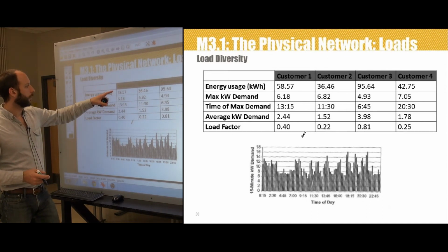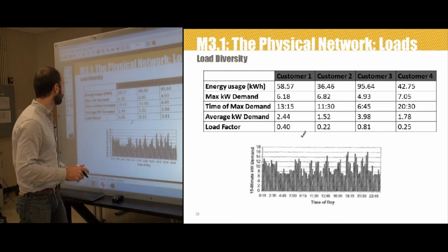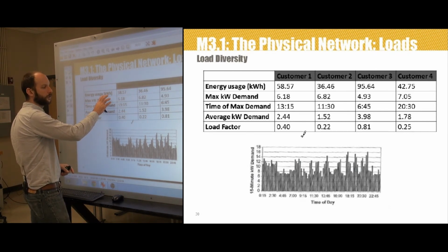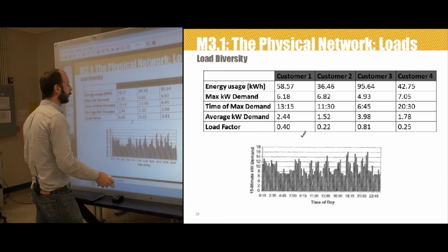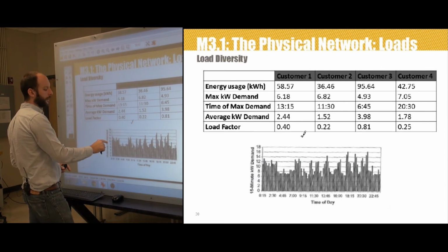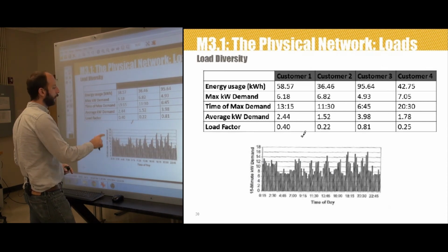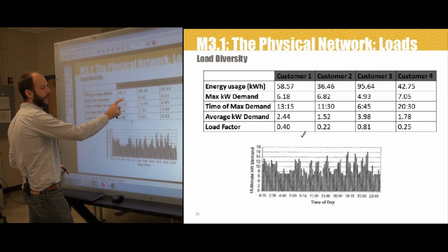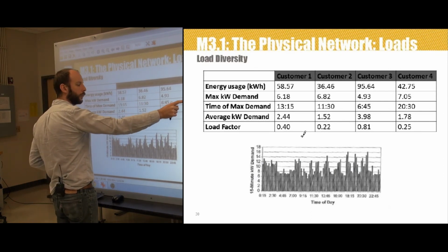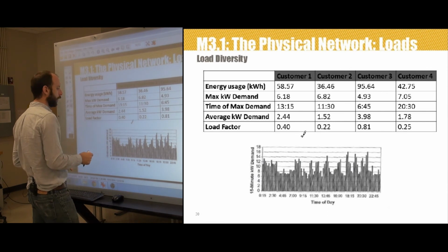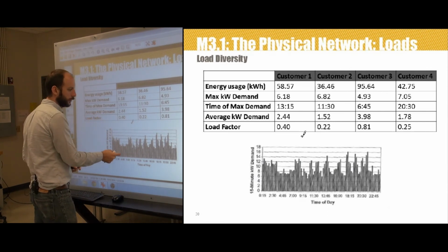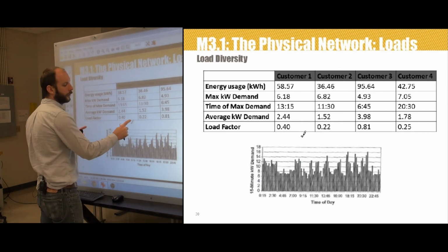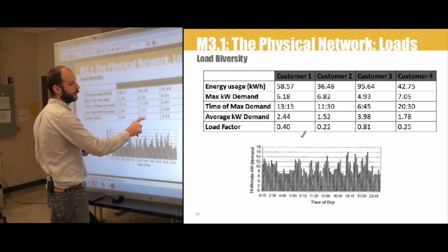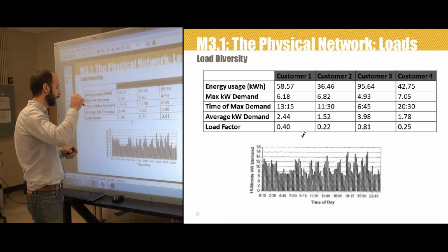What we've got is customer 1, customer 2, customer 3, and customer 4, and they all have different energy usage. Remember, that's the total amount used over the course of the day. They've got different peaks. That's the biggest one. They've got different times that the peak occurred, right? They weren't what we would call coincident. They all occurred at different times. And then they've got different averages, right? And then also different load factors. We've got a relatively low factor. We've got a really great load factor of 0.81 here.